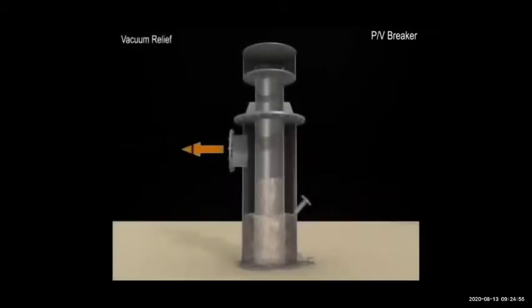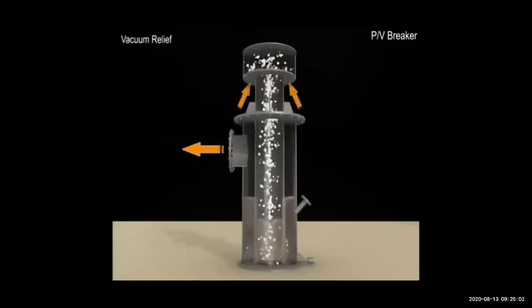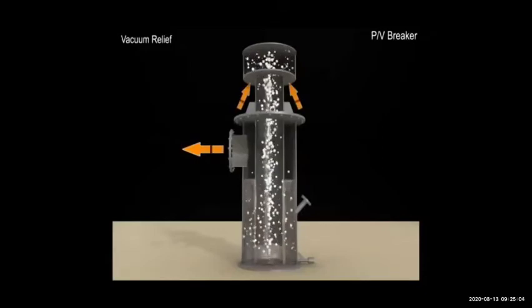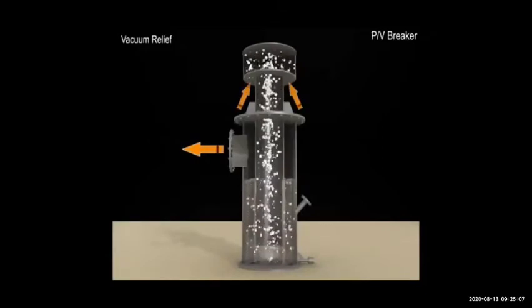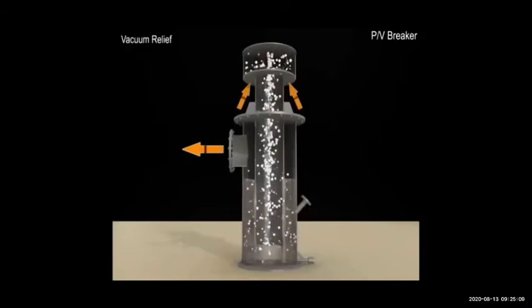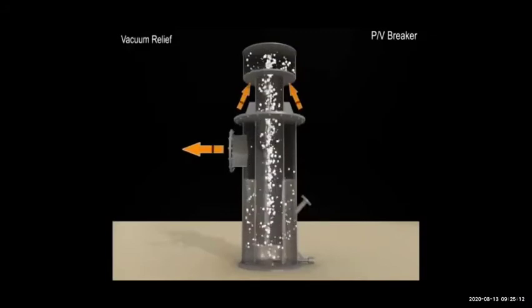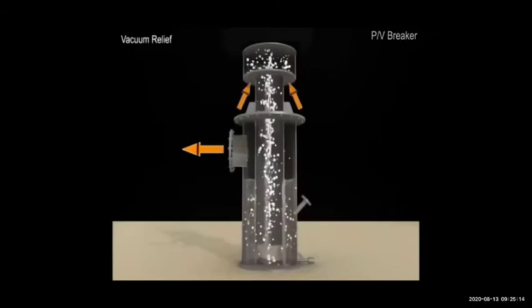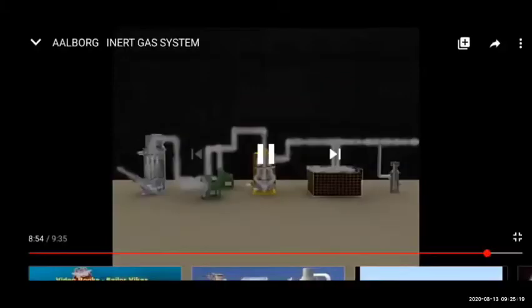If there is a vacuum in the tank — very low pressure for some reason — air will come from outside, pass through the water in the PV breaker, and go into the tank so the tank will not get ruptured. This is your inert gas system.